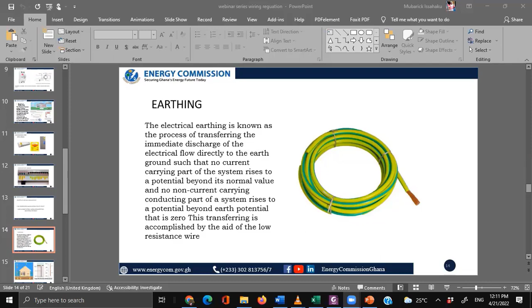It could be that the live part of the fridge is touching the metallic body, or it could be the neutral part touching the metallic body. The neutral also returns current back to the distribution transformer, but when it's returning current and touches the metallic body of an appliance, an earth fault can also occur. So it's not just the live part, the neutral can cause that too.